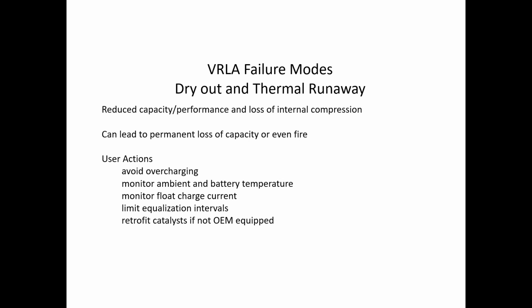We've been deployed. As a matter of fact, we just came off a thermal runaway situation at a utility in New York. The battery was 170 degrees Fahrenheit, drawing 25 amps, and it was a 600 ampere hour battery. It doesn't happen overnight, there are always indications of it, and it's a slow kind of creep, but then it just takes off. So this is a battery that wasn't looked at for months.